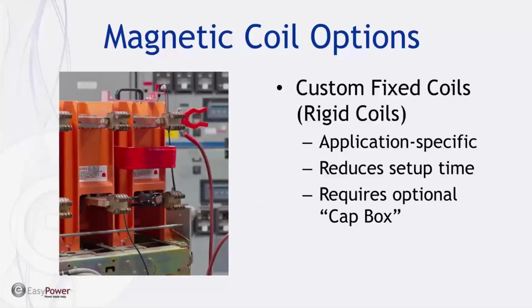And then we have some special application coils, which we call rigid coils. These are for applications where these type of fixed coils can be used. In most cases, they can't be put around the vacuum interrupter because of a line to load insulator or an insulator connected to the frame. But in this example case, we were able to make a custom fixed coil that fits directly over the insulation of the circuit breaker and makes the test much quicker.